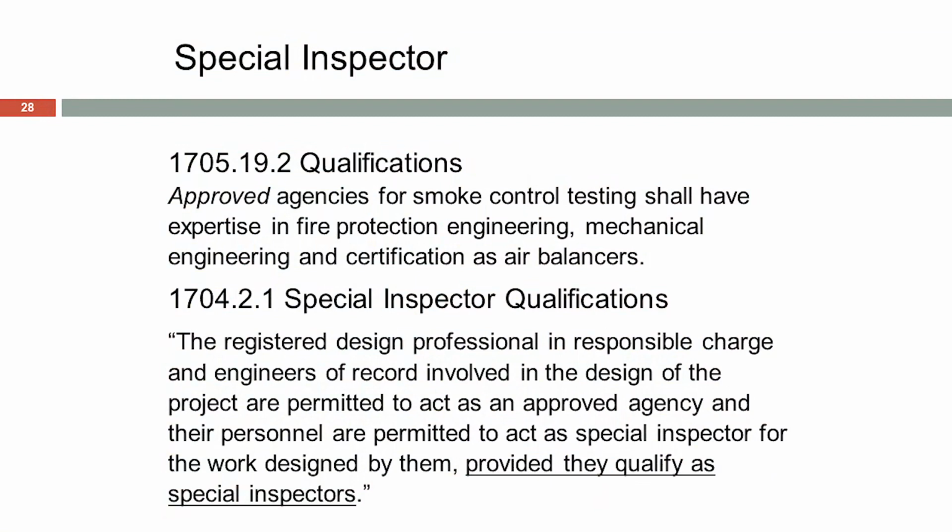Approved agencies for smoke control testing shall have expertise in fire protection engineering, mechanical engineering, and certification as air balancers. So that's an interesting concept. You must be certified as an air balancer but you only have to have knowledge and expertise in fire protection engineering, mechanical engineering.